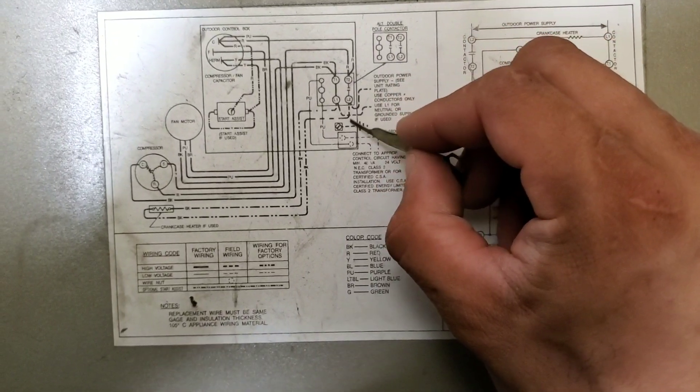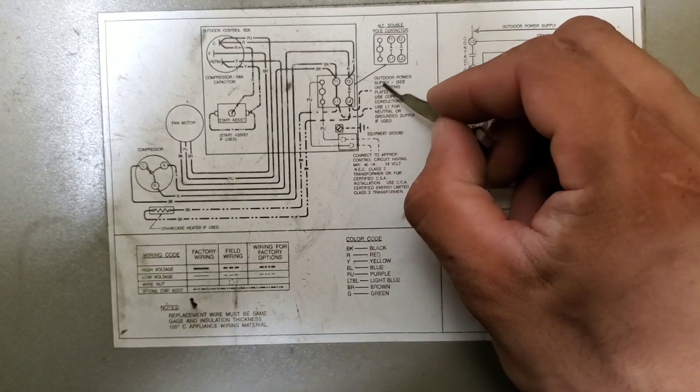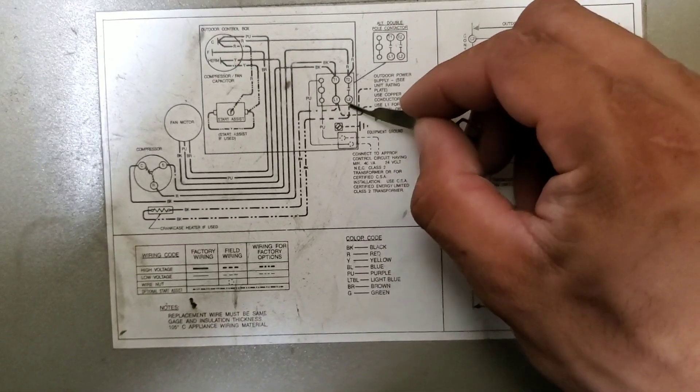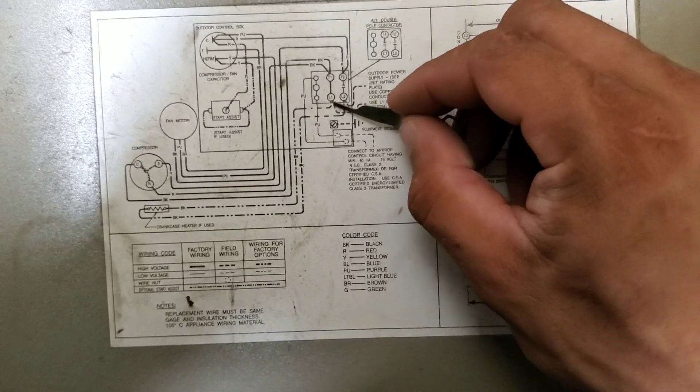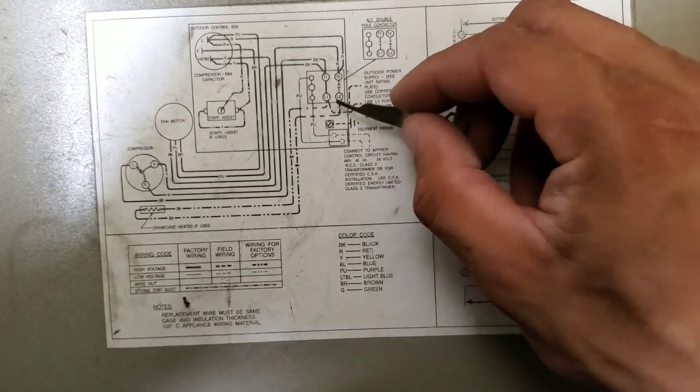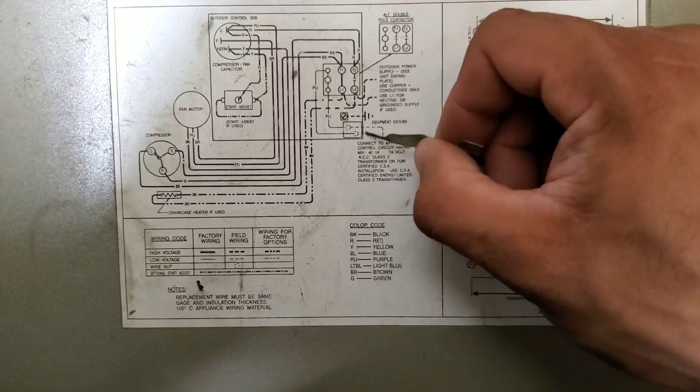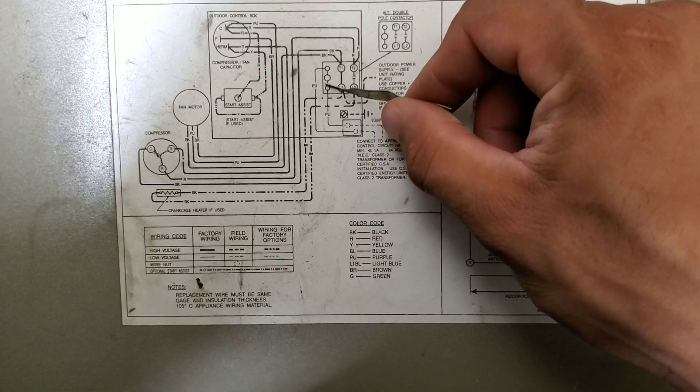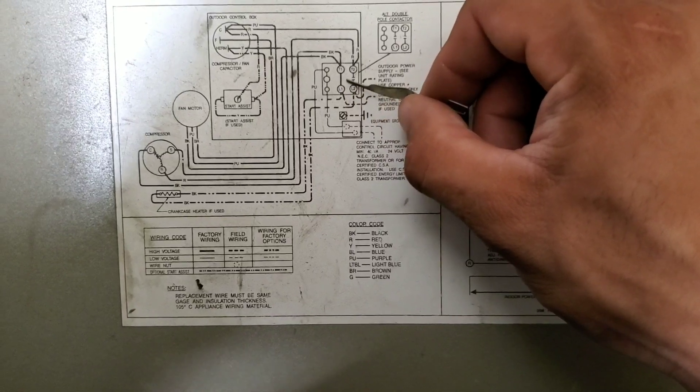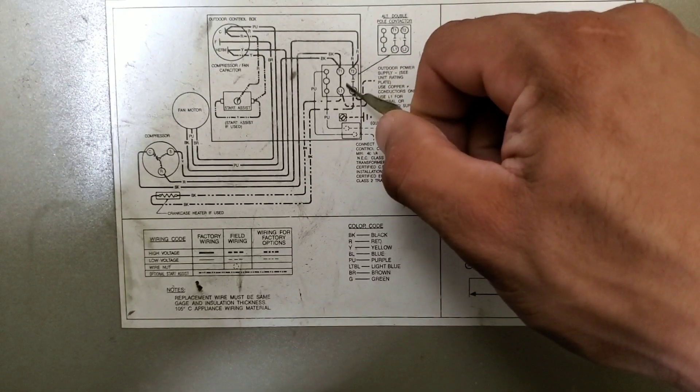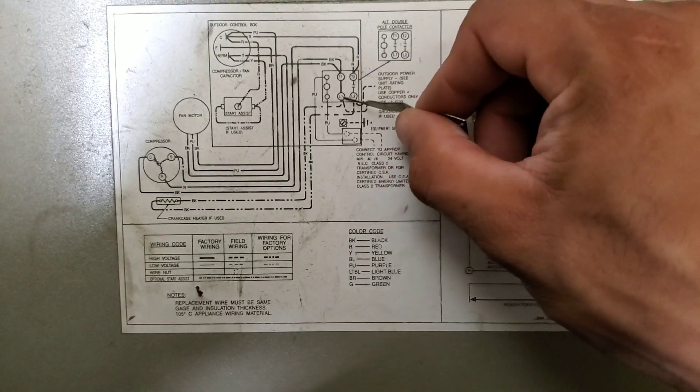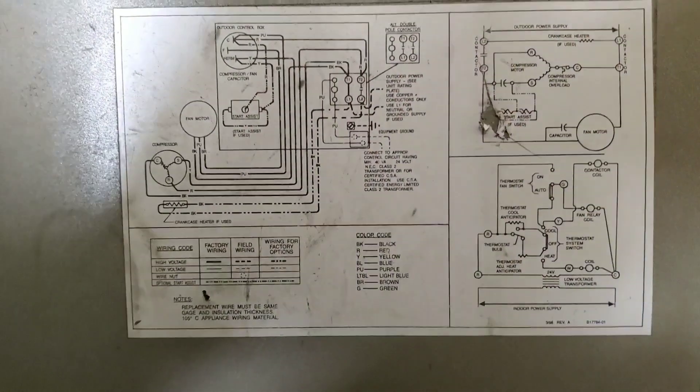Your L1 and L2 are your outdoor power supply, the 240 volts coming in, 120 on each side, that feeds to your contactor. Once your low voltage energizes your contactor, the incoming voltage goes up and feeds to the compressor.